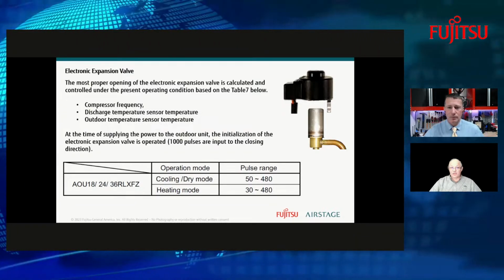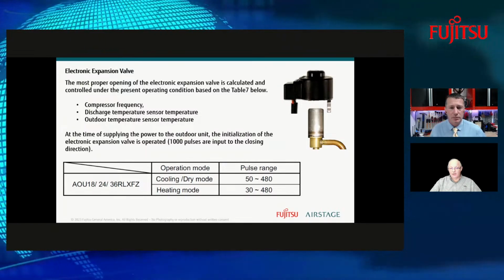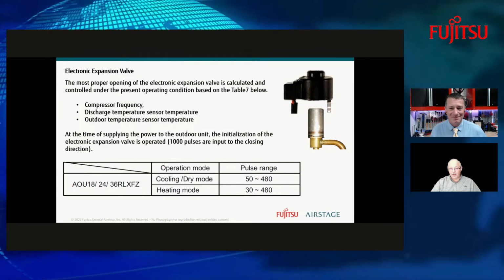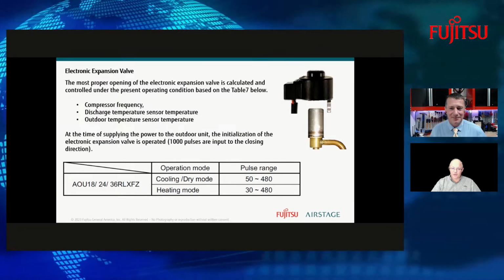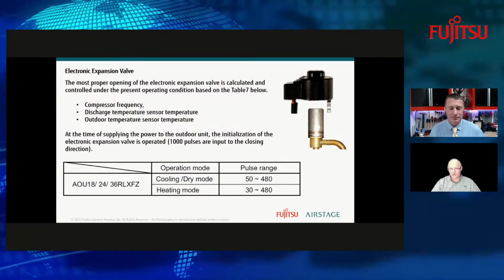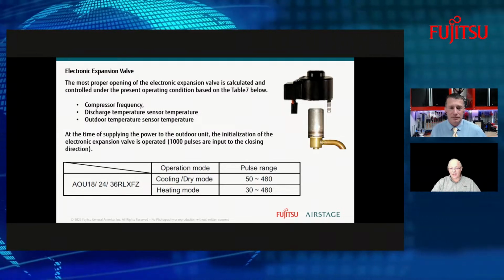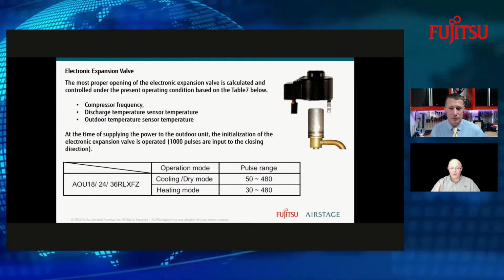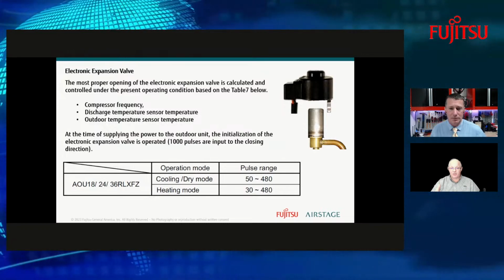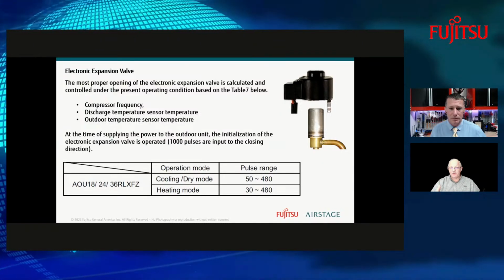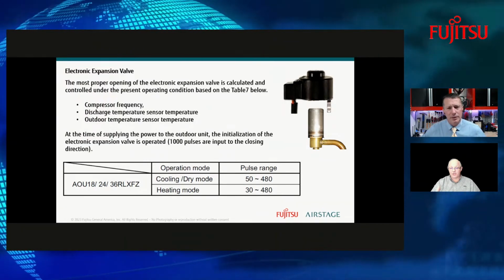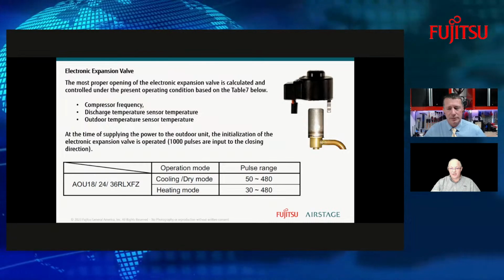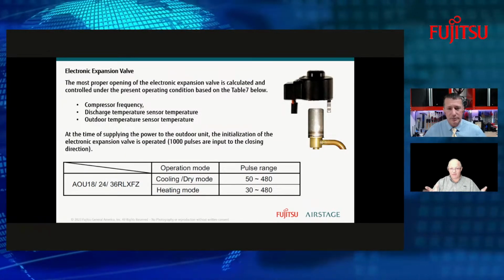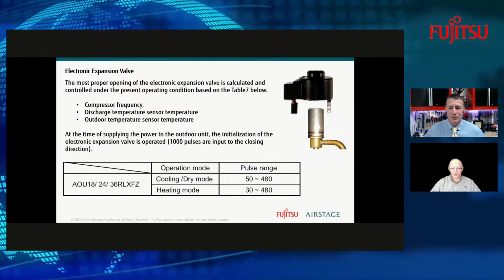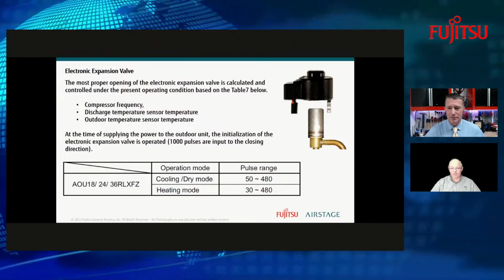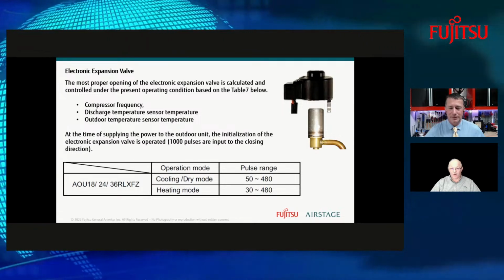Yeah, definitely. So what's happening again is we're looking at what's going on with the compressor frequency, what's happening with the discharge temperature sensor, and what's going on with the outdoor temperature sensor. That is information that tells us exactly where we need to go. Now, if we're talking about the initialization of the expansion valve, you can see here it says that 1,000 pulses are input to the closing direction. So it will reinitialize and reset itself on startup. That's just part of how engineering works with how it starts up in different modes, and then what ranges they run through.